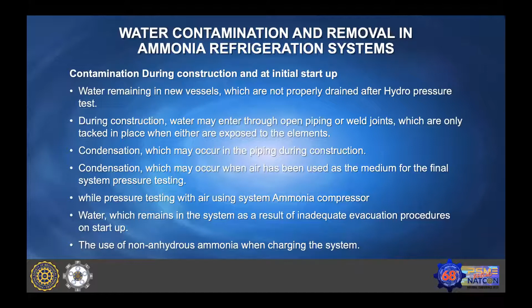And secondly, when we are charging the ammonia, we do not know the purity of the ammonia. It may not be anhydrous ammonia. Many times when the ammonia is delivered on site, it contains water. And to take the maximum benefit of the ammonia in the cylinder, the charging team tries to rotate the cylinder 180 degrees so that they take out all the ammonia. At that time, whatever water is inside the cylinders also enters the system.